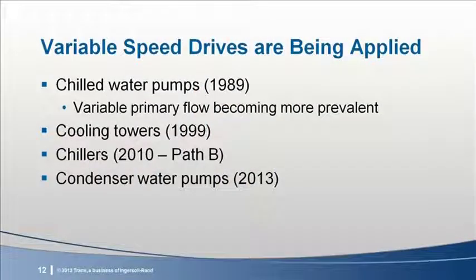As variable speed drive costs came down and reliability increased, VFDs started to become more prevalent on all components in the system. Once use began, the results led to changes in standards and codes. Let's take a look at how these changes made their way into ASHRAE IES Standard 90.1 through 2010. A little later, Susanna will touch on changes for the 2013 version of the standard. Let's start with chilled water pumps.